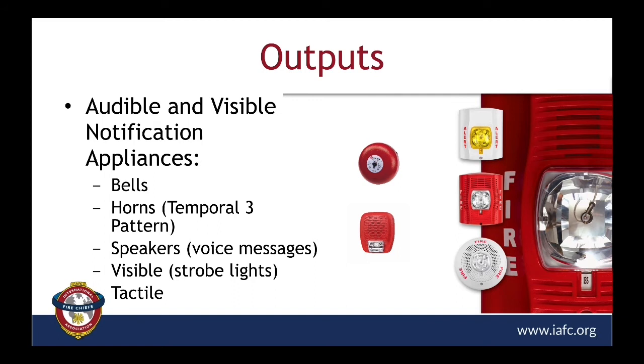I think that there's not a significant reduction in the requirement to install these, but certainly, some jurisdictions are having problems with nuisance alarms, and they may want to eliminate them, and the code does have requirements, especially in K through 12 schools, if you want to eliminate or reduce pull stations. So the code does address, for certain occupancies, if they want to reduce the number or the placement of pull stations in a particular type of occupancy. Great, thank you.